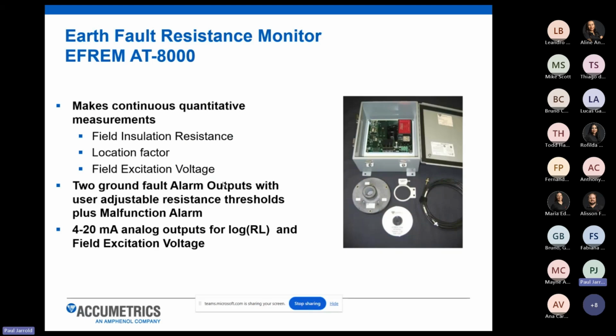So we're going to talk about our main product to monitor for ground faults. It's our AT8000 EFREM system. EFREM stands for Earth Fault Resistance Monitor. It makes a continuous quantitative measurement of the field insulation resistance and the excitation voltage, and we also have a feature in our system called location factor, which is a design troubleshooting piece of our equipment that allows you to predict approximately where in your generator field the fault has occurred.